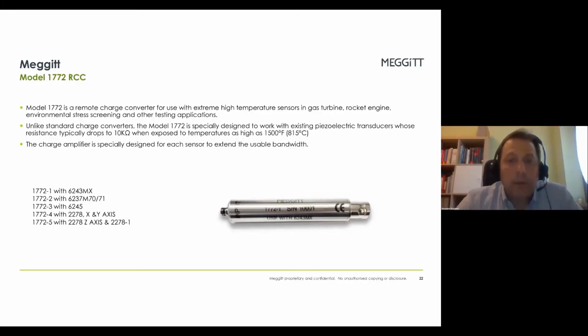This unit has multiple features. First, it's designed to be used with a Meggitt unit, in particular because it features TRS, transducer resonance suppression circuit, which electronically cancels the transducer's resonance. This lets us extend the usable bandwidth of our unit, which is why it's set to work with a specific unit only.